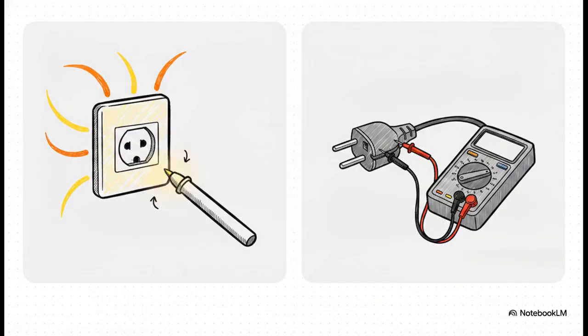Now, how you actually carry out your procedural steps completely flips depending on the state of the installation. For instance, when we test for polarity, the method is entirely dictated by the supply. If the supply is connected and live, you've got to use a high impedance voltage indicator to carefully test between the active and neutral to ensure correct polarity. But if the supply is not connected, your method changes completely. You verify isolation, and then you use your trusty low-reading ohm meter to measure resistance, usually by making a temporary connection at the switchboard. The context dictates the tool, and the tool ensures the safety.